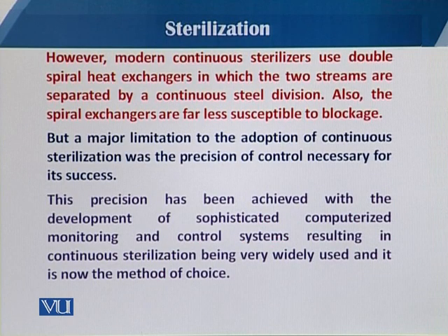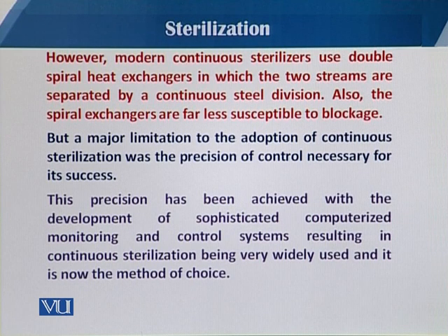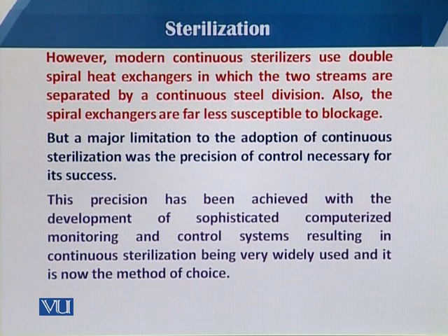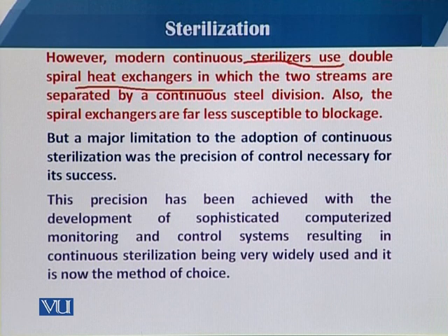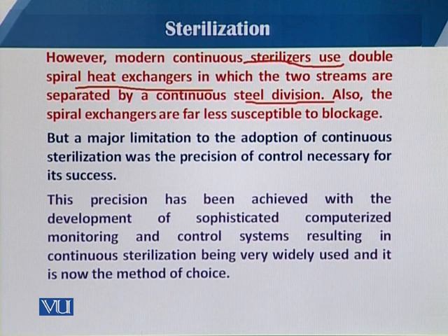Modern continuous sterilizers use double spiral heat exchangers in which the two streams are separated by continuous steel divisions, eliminating the risk of mixing sterilized and unsterilized streams. Spiral heat exchangers are also far less susceptible to blockage compared to plate heat exchangers.